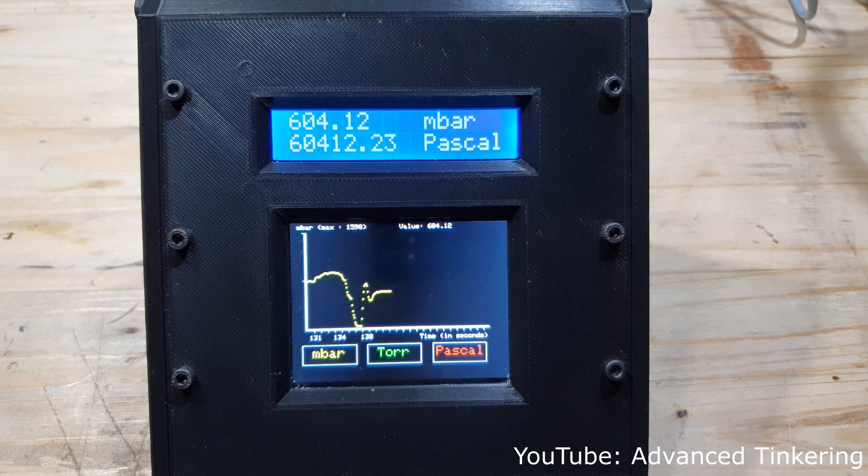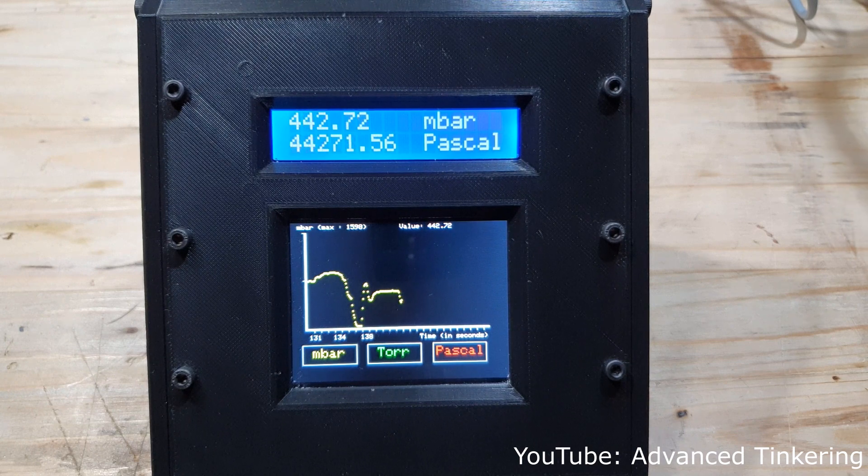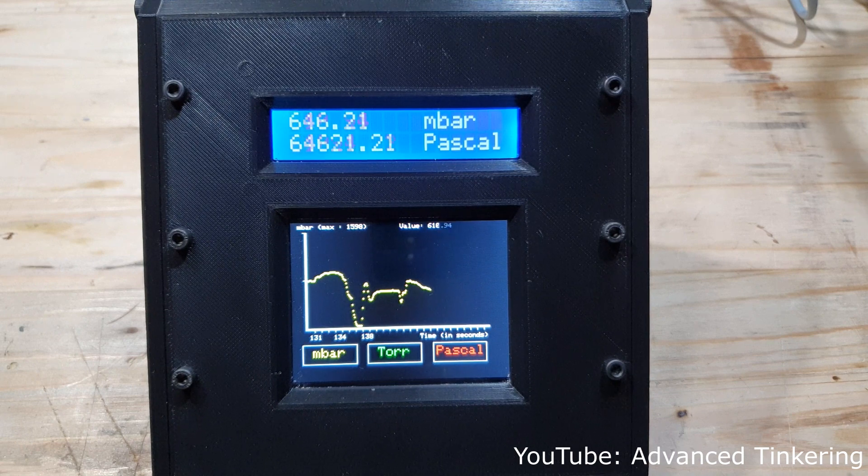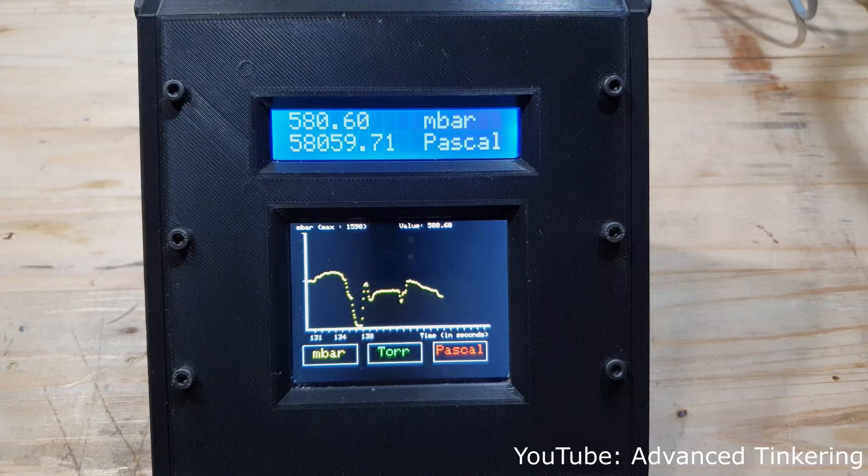Another great feature of this controller is that you can use a USB cable to connect it to your PC and use the serial print function to plot the pressure against time in, for example, Excel.